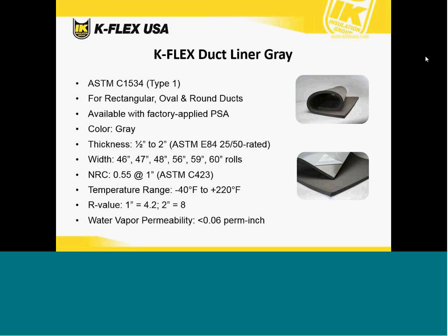Next is K-Flex Duct Liner Gray. This is to the ASTM C1534 Type 1 standard. Available for rectangular, oval, or round ducts. Available with or without the factory-applied pressure sensitive adhesive. The gray is available in thickness from 1/2 inch up to 2 inches, all 25/50 rated by E84. Standard width product is 46, 47, 48, 56, 59, or 60-inch rolls, depending on the coil line that it will be run on.